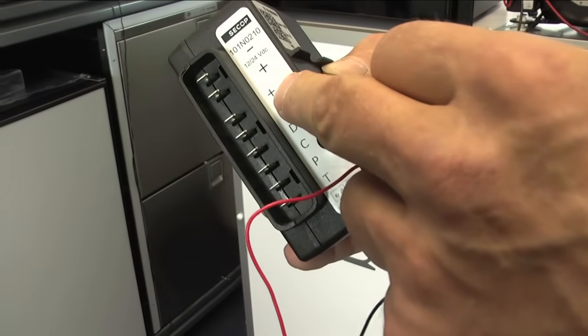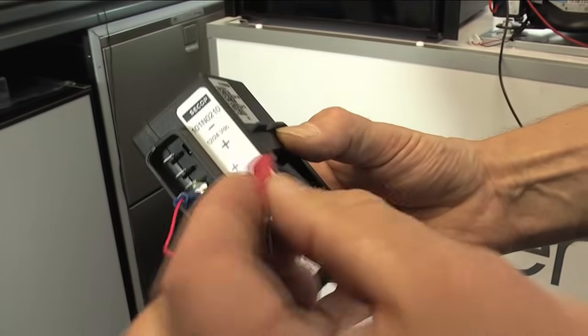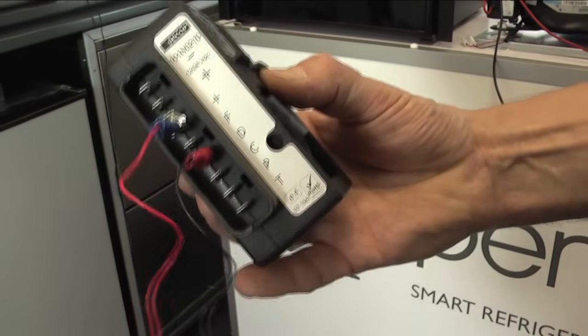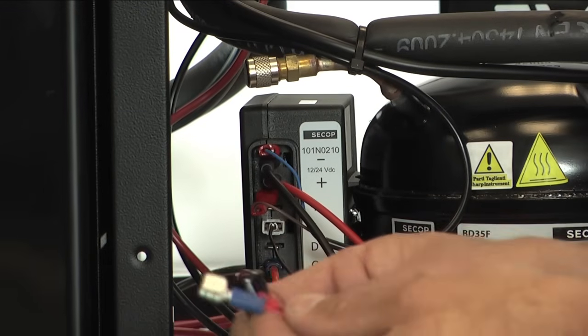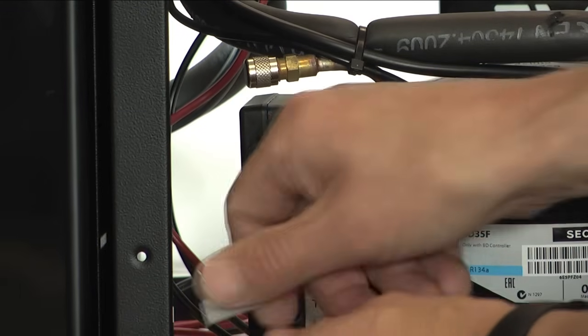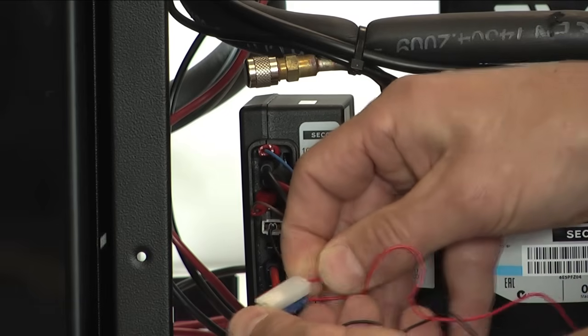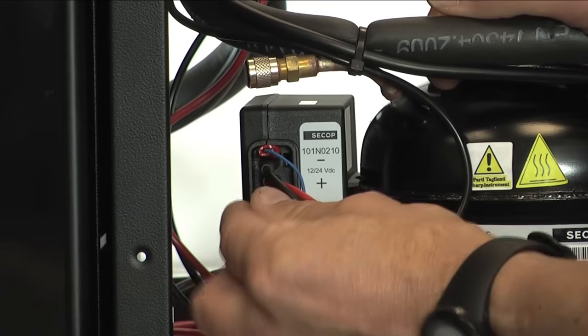So the positive goes on the small plus, which is shared by the fan, and the negative goes on the D for diagnostic. I'm now going to connect the LED onto the problem compressor in the same way, but this time I'm going to add the fan onto the positive of the LED so that we've got everything connected.